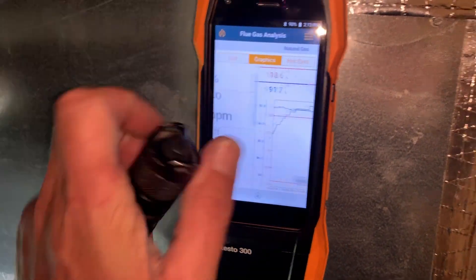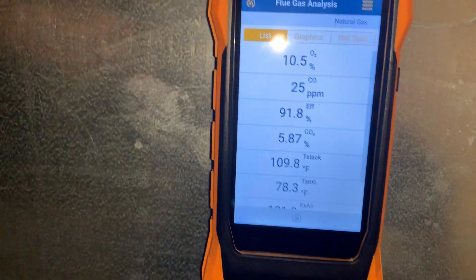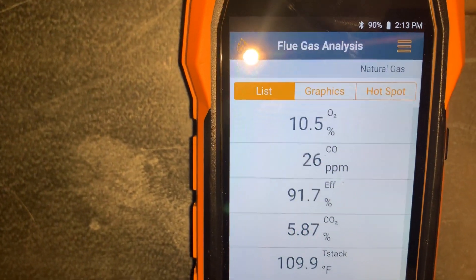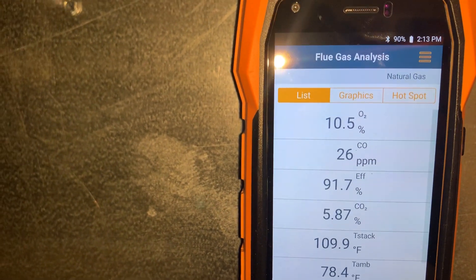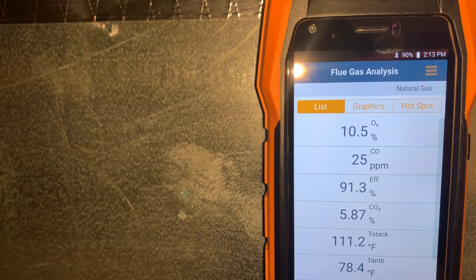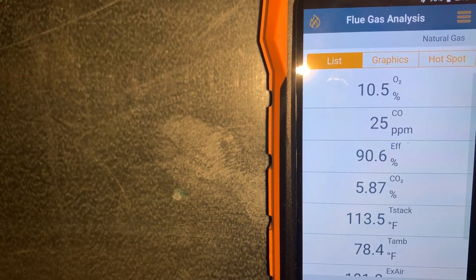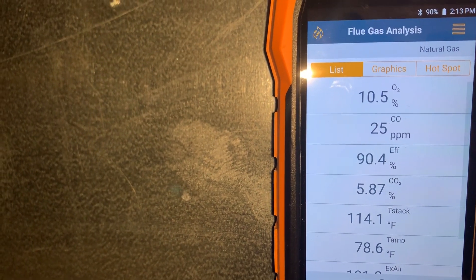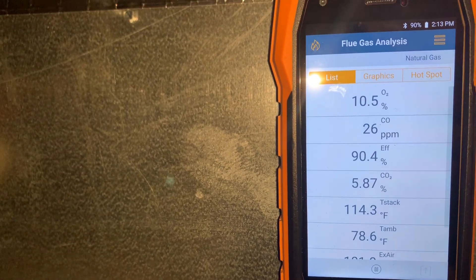So we're doing a combustion analysis with the Testo 300 — this is the brand new model for the US. Taking a look at these numbers: we have 10 and a half percent oxygen, our carbon monoxide is at 26 parts per million, which is acceptable. My general rule of thumb — anything under 50 is considered acceptable, and let's try to get that down as close to zero as possible. Right now the gross efficiency is 91 percent and dropping — 90.5 percent — our CO2 at 5.87 percent, and our stack temperature is 114 degrees.